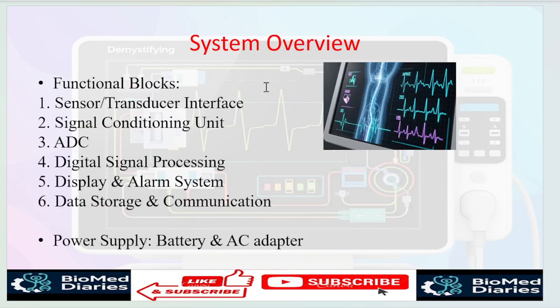So the overview of patient monitor systems. The patient monitor has various functional blocks, which consist of sensors and transducer interface, signal conditioning unit, analog to digital converter, digital signal processing, which we will see in the next videos, of how digital signal processing is used in the patient monitor, display and alarm system, and data storage.